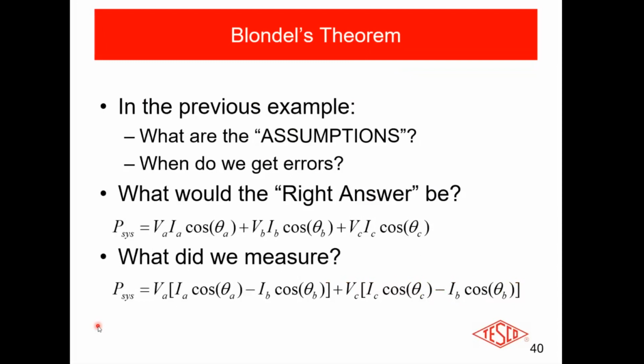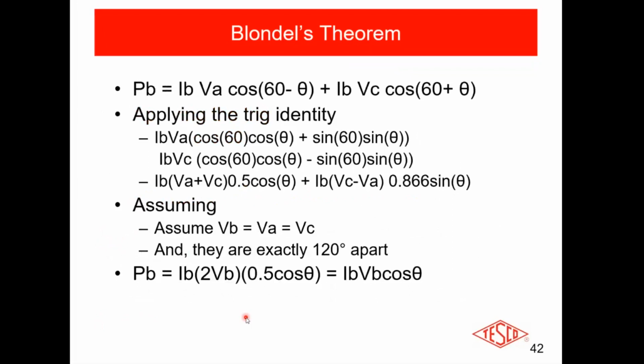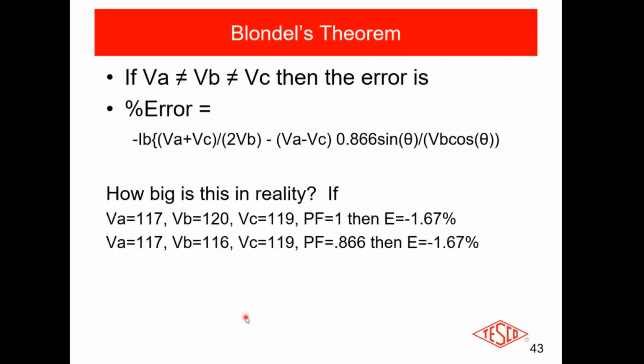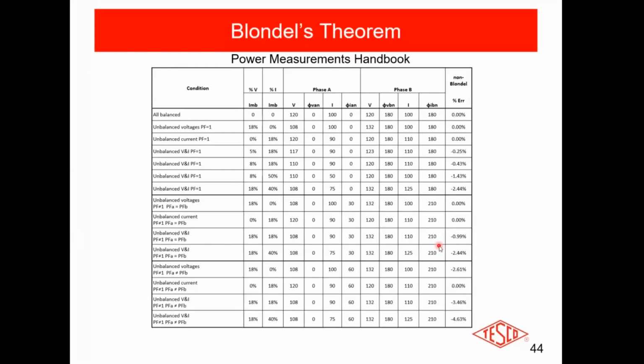All right? So I'm not going to torture you with the math, but it was too much fun to put it up here. So we have a couple of things. In the previous example, what are the assumptions or the perfect conditions, and what's the right answer? The right answer for the power measurement is this, and what did we actually measure is this. What the heck does that mean? I can do all the math, and I could come up with all this good stuff, but what does it really come down to? And the answer is, how big is this difference? Well, if I have a voltage difference of 117, 120, and 119, not a big voltage difference, and a power factor of 1, I lost about 1.67%. If I got a power factor that's less than that, but my voltages were a little closer together, I also still lose 1.67%. So this is with everything working correctly.